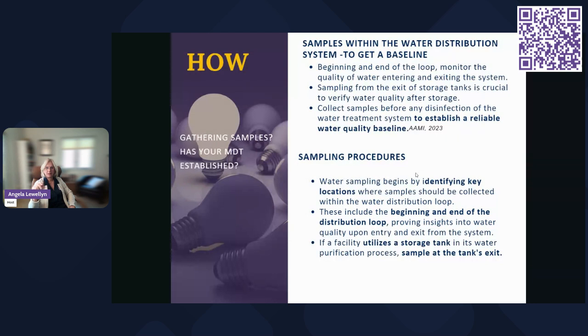Water sampling begins by identifying key locations. This includes the beginning and end of every distribution loop, before treatment, after treatment, and at the point of use — whether that's the third bay sink at your critical point, or samples your facility engineers or a third party can also get from the back of a mechanical washer.